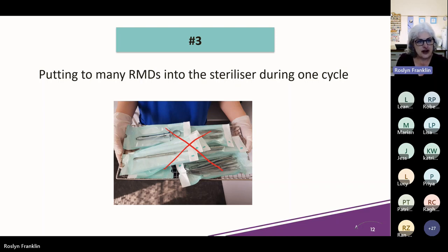That's because of the way our steam sterilizers and pouches work. We need the pouches in a single layer so the steam can cover them completely. Those bags actually undergo quite an expansion in the autoclave, and you need them in a single layer so nothing impedes the steam getting in.